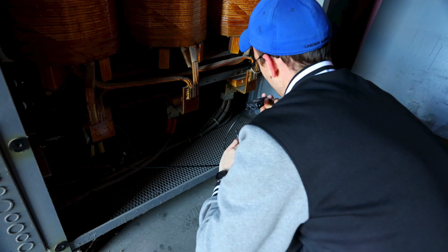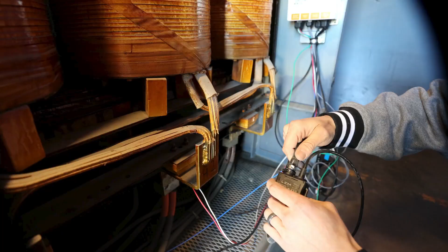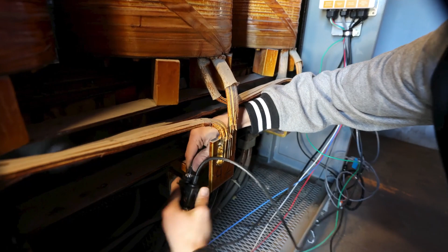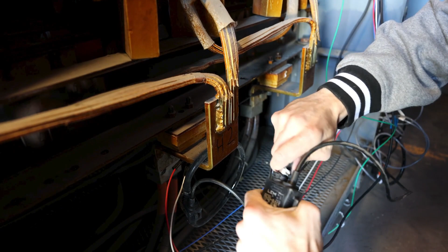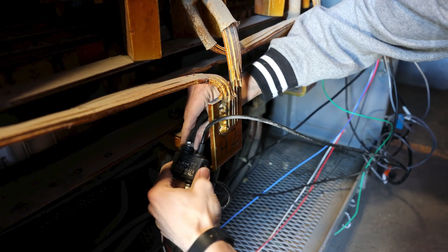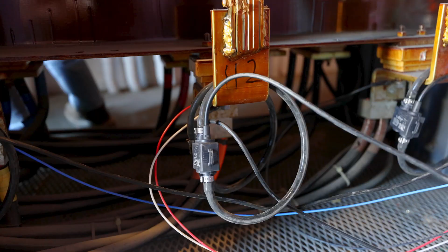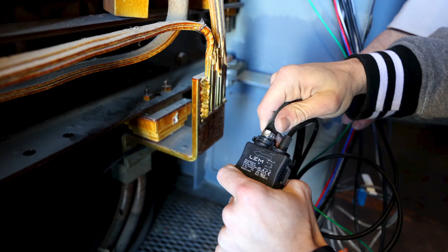Next, we're going to do the same thing for H2 or B phase. Again, since this is a three-wire system, we have the neutral and the B phase ring CTs put on here, the Rogowski coils. So first I put on the B phase, and second I put on the neutral one. And like before, you break the bracelet apart and then put it around your bus bar, get the arrow pointing in the right direction, and then place it back onto the bus bar.